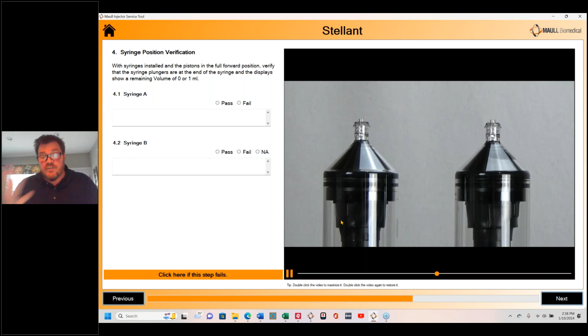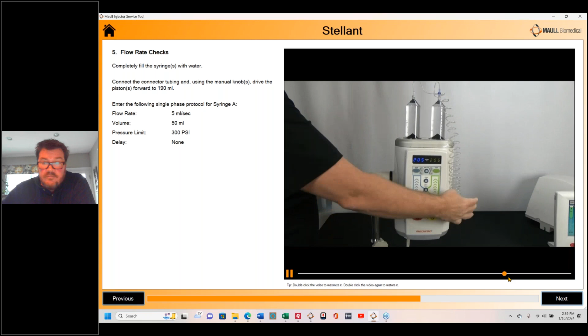Next, we're going to do flow rate checks. We're all BMETs. I think we all know what a flow rate check is. So we're going to enter a specific protocol: flow rate of 5, volume of 50, pressure limit of 300 psi. This is actually how we fill the syringe. I don't think we've demonstrated this yet. And do that for both syringes. Once we're done, we're connecting our connector tubing. Then we are going to prime our connector tubing. Then we're actually going to perform the actual flow rate check.